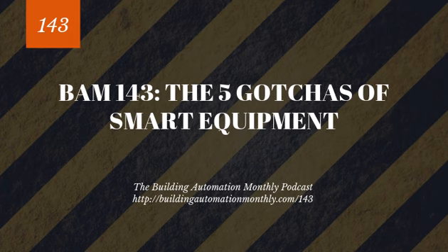Well, were you there when they were setting it up? Did you tell them what baud rate you're at? Because you can't complain that they put it on a different baud rate, or used a duplicate MAC address, when you're not giving them any information about your design. So you've got a part in this too. You've got to go and be like, hey, this is the baud rate we're using. These are the MAC addresses that are available. By the way, this wire is positive. This wire is negative, etc., etc. You've got to be engaged when this is all getting started up.